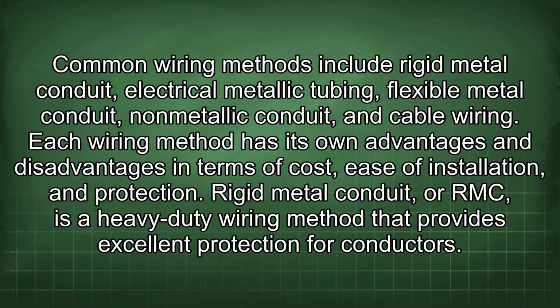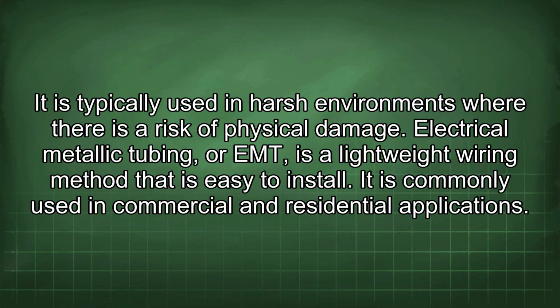Rigid metal conduit, or RMC, is a heavy-duty wiring method that provides excellent protection for conductors. It is typically used in harsh environments where there is a risk of physical damage. Electrical metallic tubing, or EMT, is a lightweight wiring method that is easy to install. It is commonly used in commercial and residential applications.